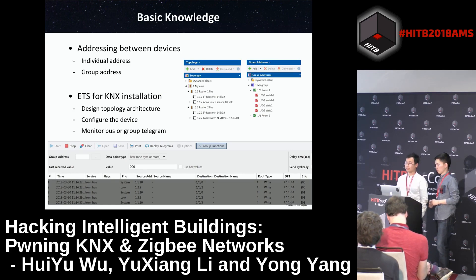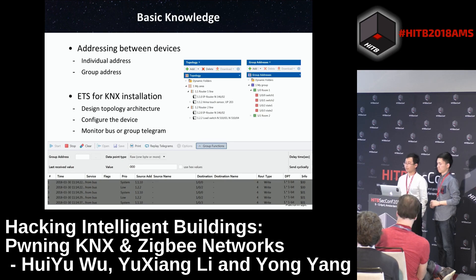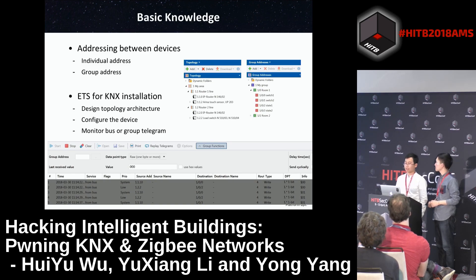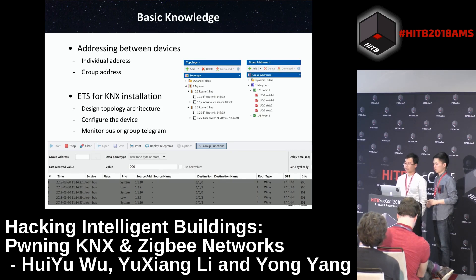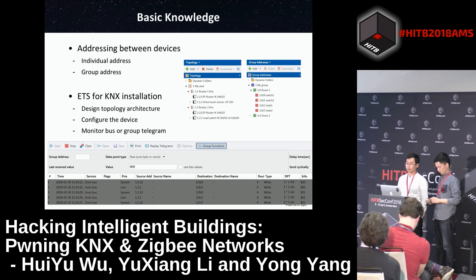Addressing between KNX devices involves two object types: individual address and group address. The individual address is used to construct the network topology; every KNX device has a unique address consisting of three numbers separated by dots, representing the area, line, and device number. The group address is used to define the functions of the KNX network. For example, if a button is pressed, data is sent and all devices bound to the group address will respond by switching on or off. Developers use ETS software for KNX installation, including designing topology architecture, configuring devices, and monitoring bus or group telegrams.